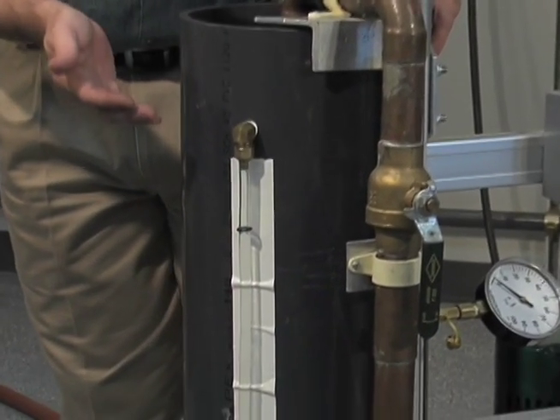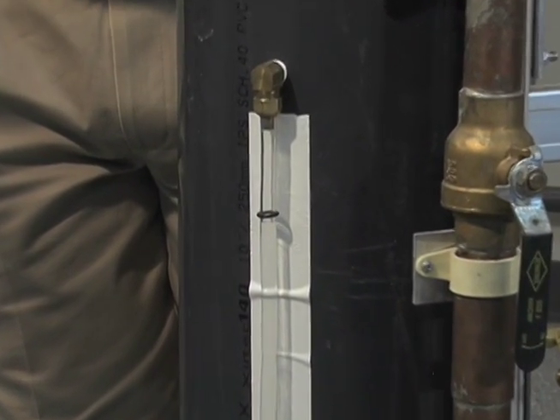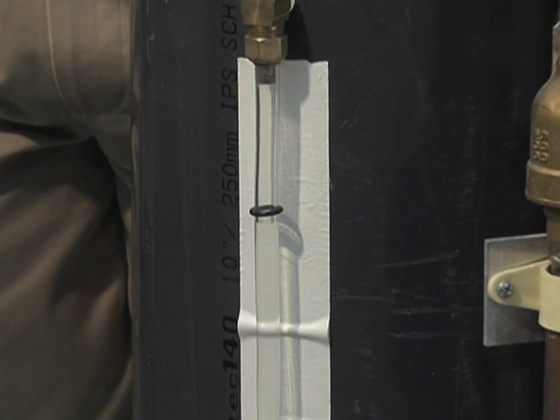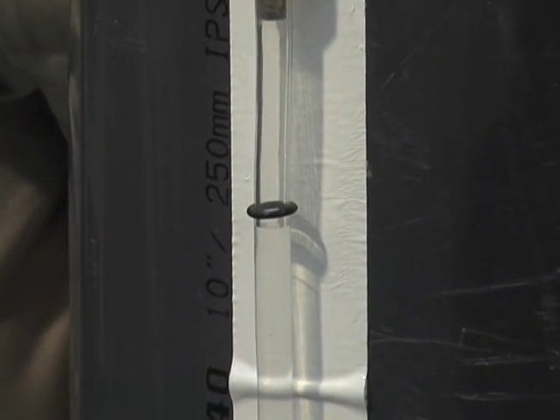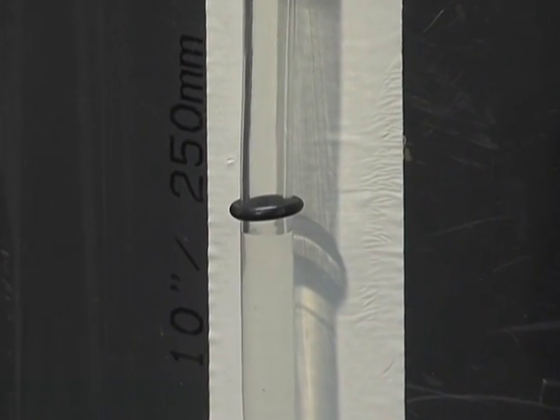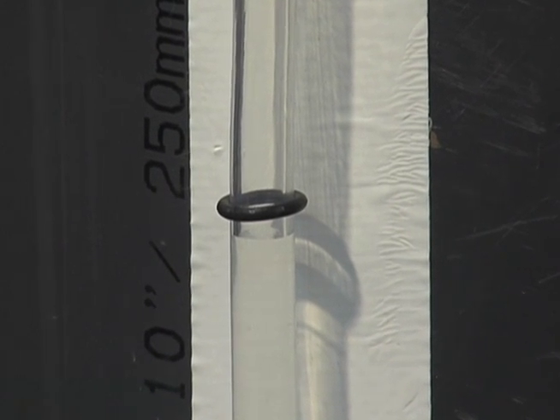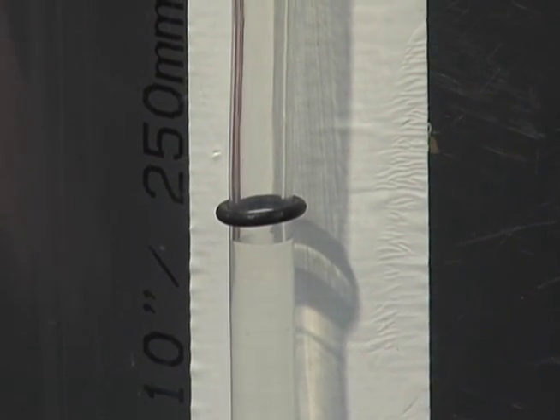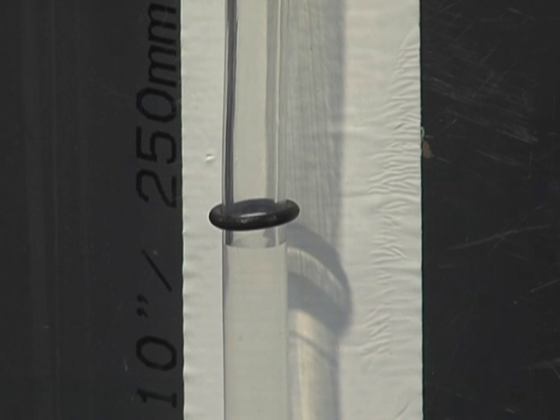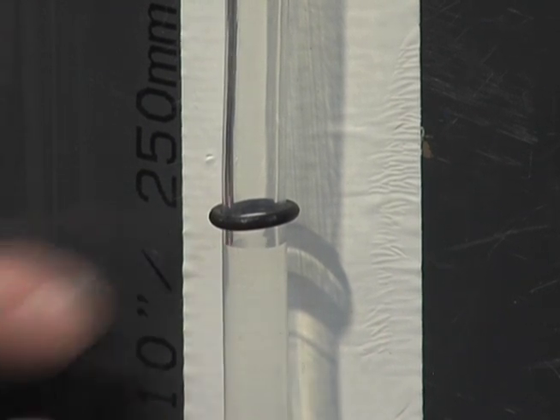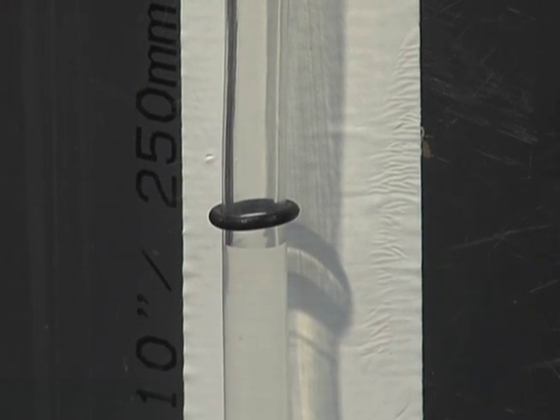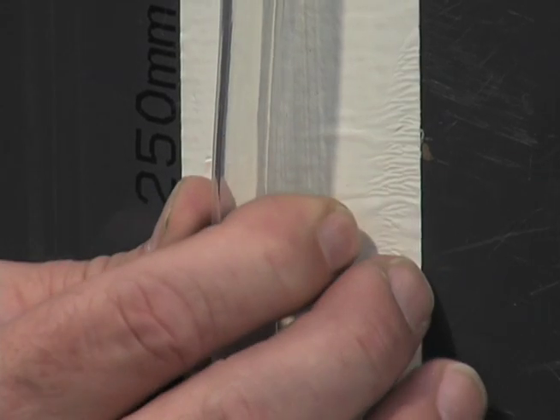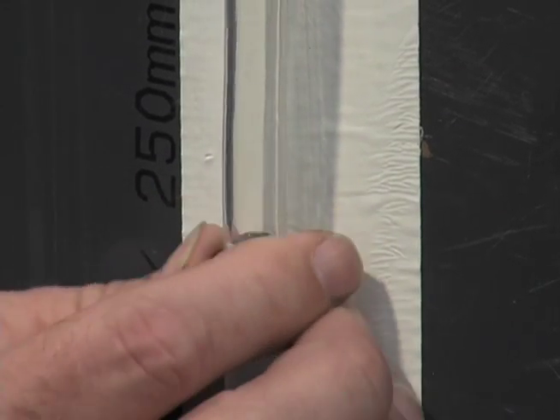Again, it's very important to use a sight glass because you're not able to look down inside a cylinder and determine if you've lowered that level. So a sight glass is a very effective method, especially when you have something like an O-ring that's going to set that sight glass. And you can see here we've moved out probably a good 1/4 of an inch. So we've dislodged some air out of this loop. So what we're going to do is reset our O-ring here, our indicator, to that level.